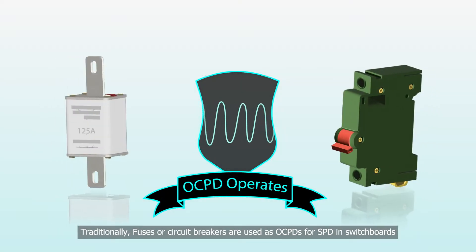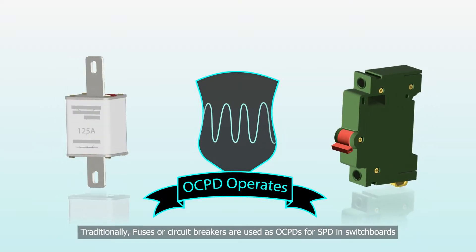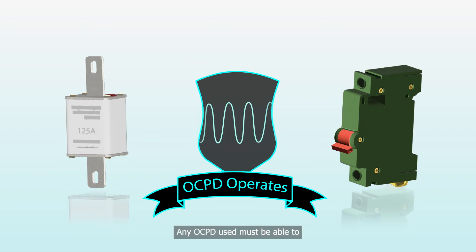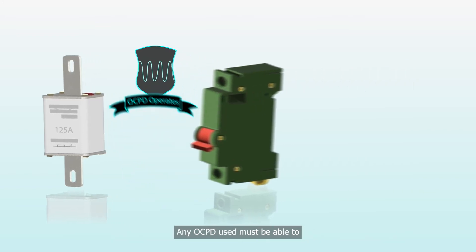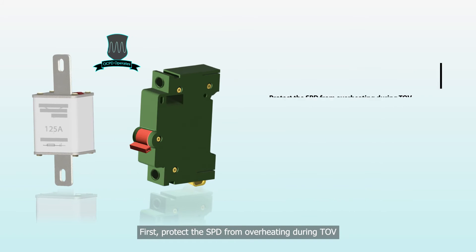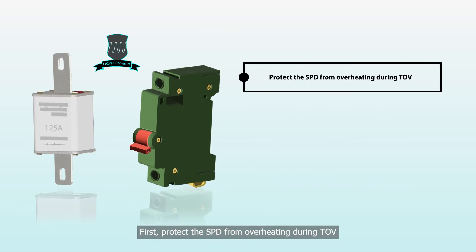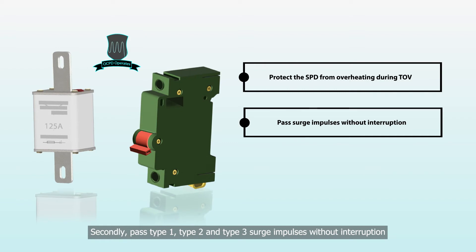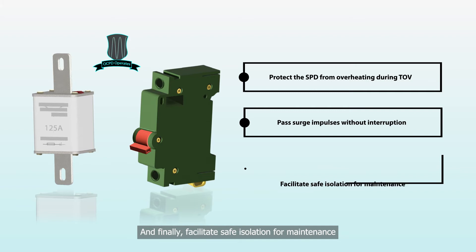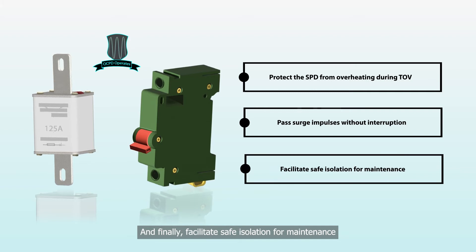Traditionally, fuses or circuit breakers are used as OCPDs for SPDs in switchboards. Any OCPD used must be able to: first, protect the SPD from overheating during TOV; secondly, pass Type 1, Type 2, and Type 3 surge impulses without interruption; and finally, facilitate safe isolation for maintenance.